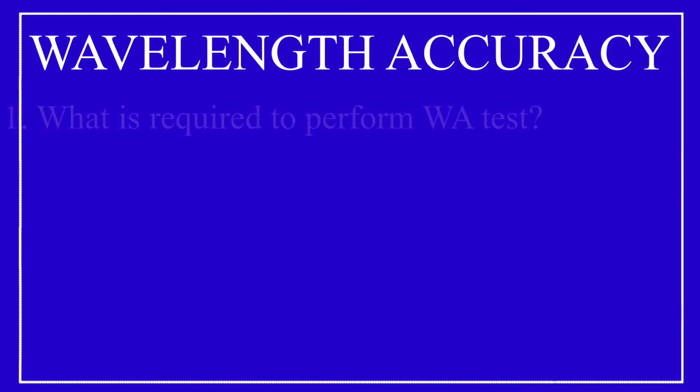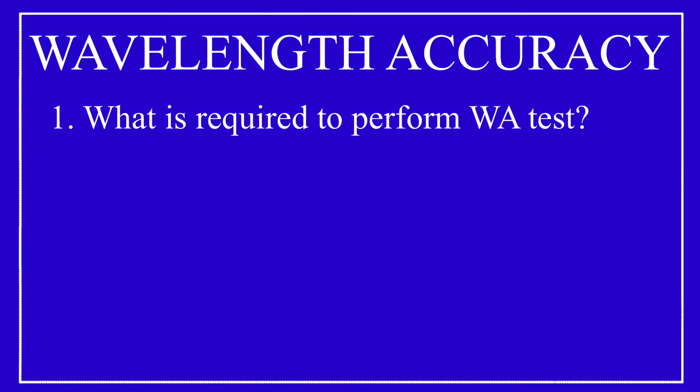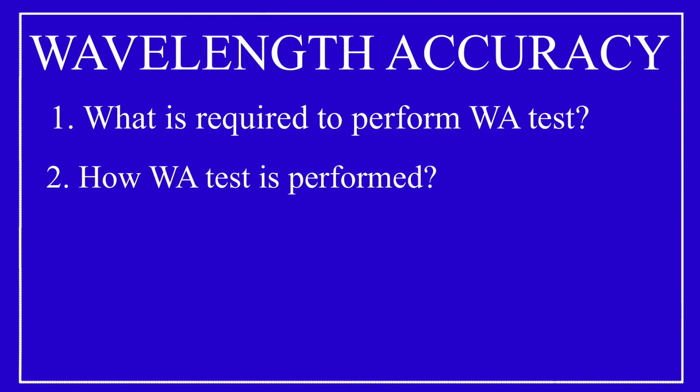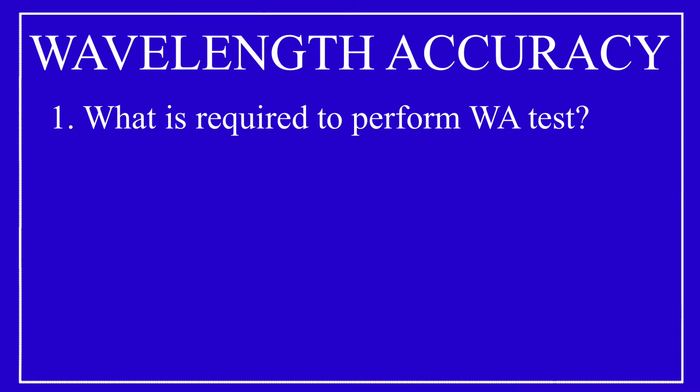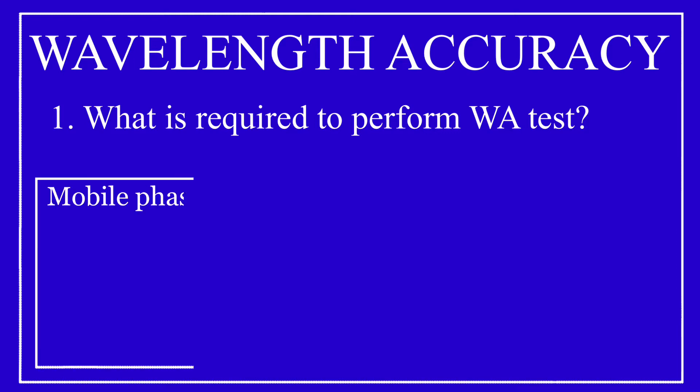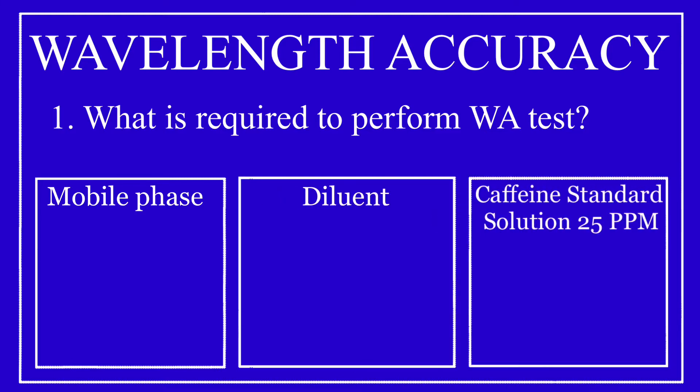In the wavelength accuracy test, we will learn three things: number one, what is required to perform the wavelength accuracy test; number two, how the wavelength accuracy test is performed; and number three, how it is decided whether the wavelength accuracy test is passing or failing. To carry out a wavelength accuracy test, we need mobile phase, diluent, and a caffeine standard solution.